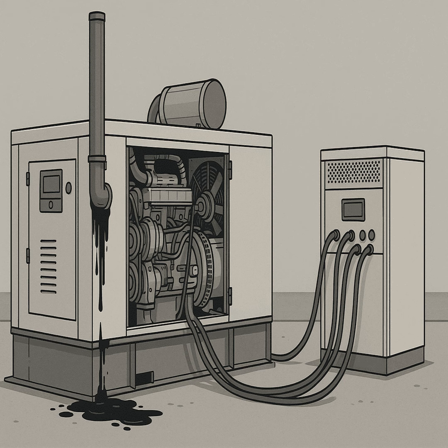Now, I heard something interesting recently that modern engines might be changing the game a bit here. You mentioned advancements earlier. Yes, this is a really important point, especially for people looking at newer equipment or managing modern fleets. Technology has come a long way. Modern diesel engines, particularly those using things like common rail fuel injection systems, advanced charge air cooling, and much tighter tolerances in piston and ring design, think engines from makers like Perkins or Caterpillar, for example, are inherently much more resistant to wet stacking. So they handle low load better. They handle it significantly better than older designs. Their combustion is just much more efficient across a wider range of operating conditions. This means that for some of these advanced generators, the traditional monthly loaded exercise might not be strictly necessary anymore. Really? What's the alternative?